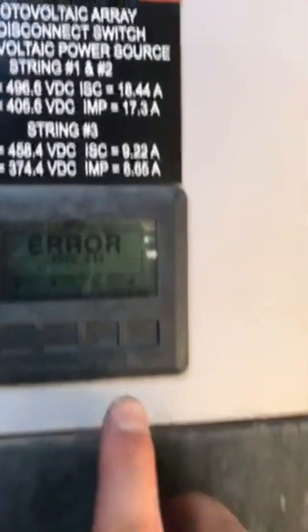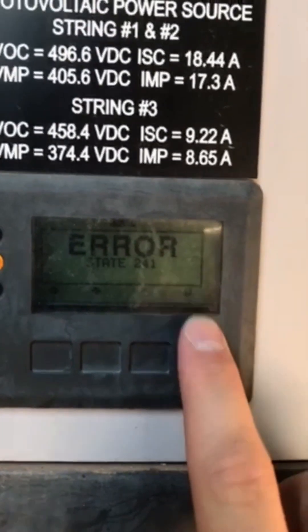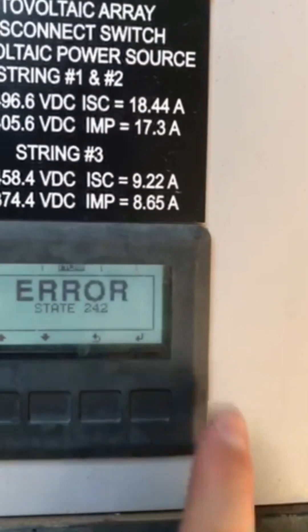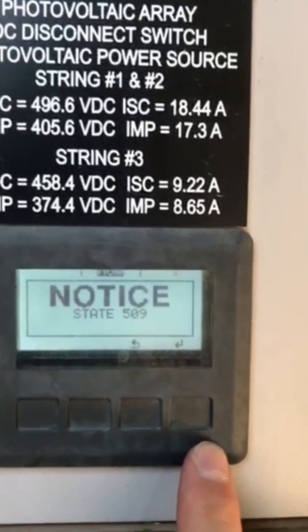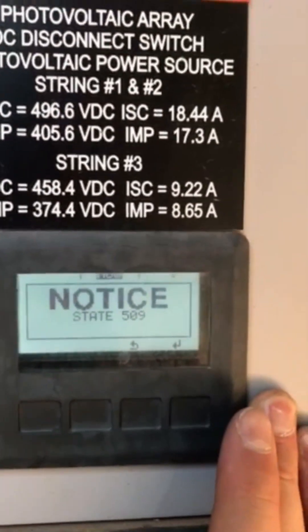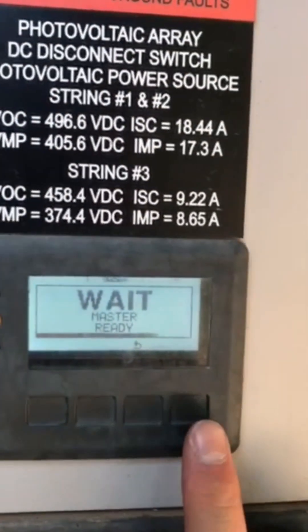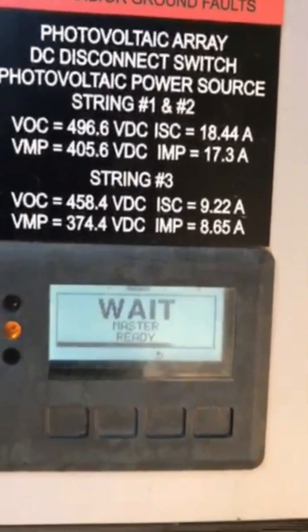This is specifically for the Fronius Primo inverter. It's kind of hard to see on the screen, but there is an enter button on the very right — you just want to hit that. There are probably going to be a couple of weird codes; I wouldn't worry about those. State 242 typically means it had a power outage or something happened with the grid voltage.